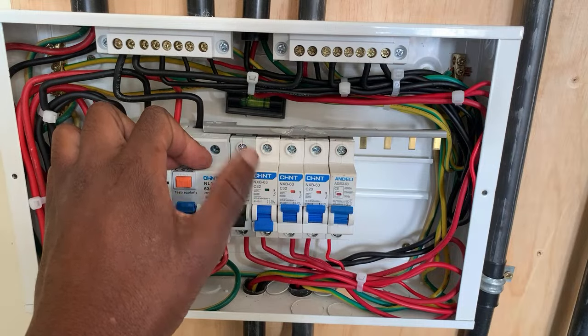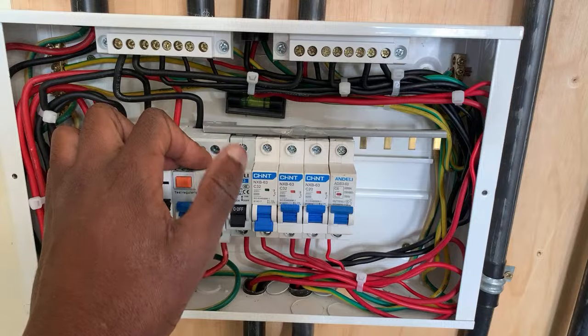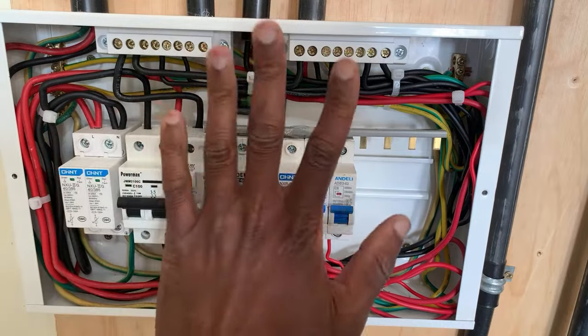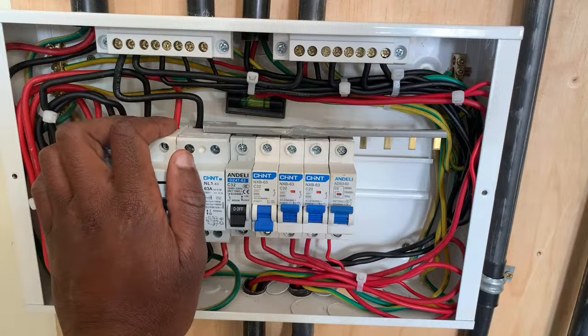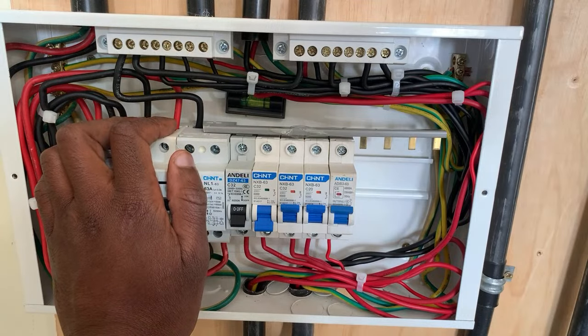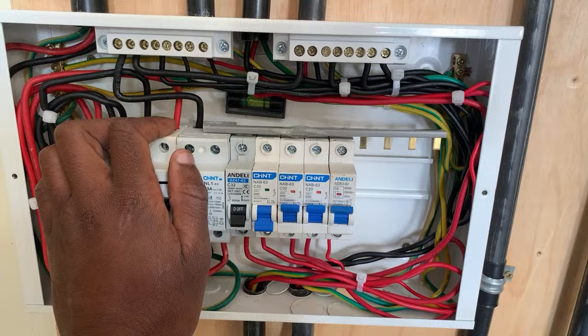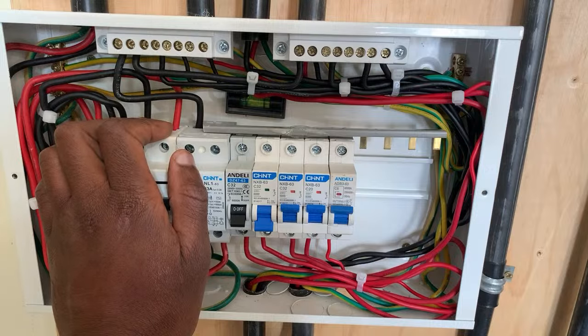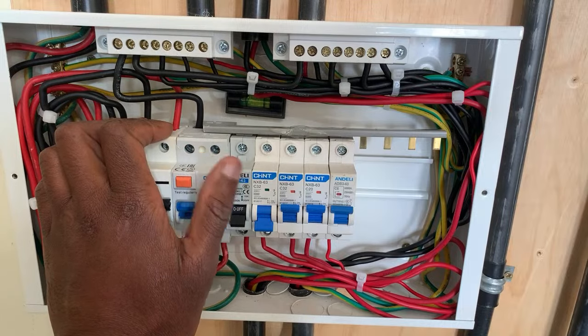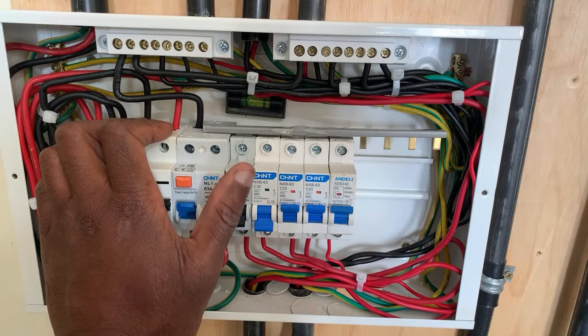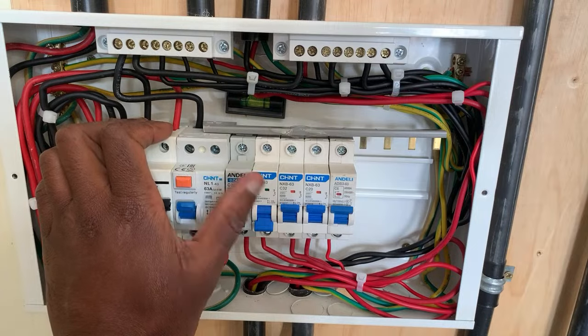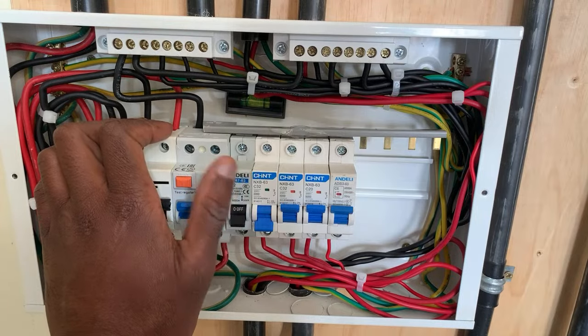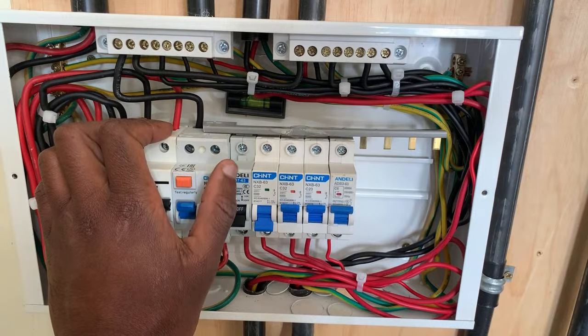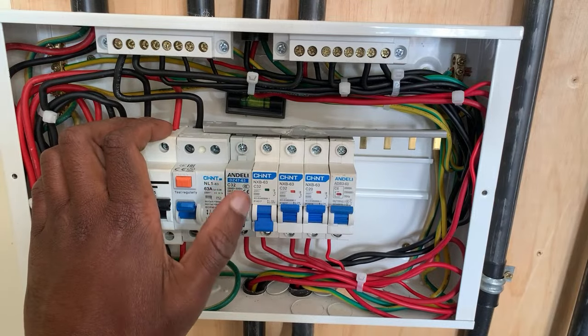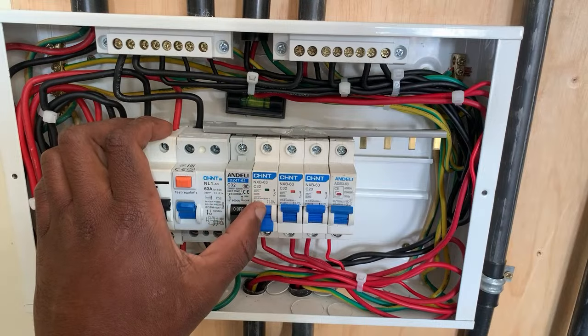So the main question should be, what specific circuit is not working? You don't start here, you start with the circuit that is not working. Is it the pump which is not pumping water? You ask those questions. At that particular time, you have already visited your customer. Is it the pump? Is it the electric cooker? You go and disconnect. Now, after you have disconnected, your job is not done. You should not lift this circuit breaker up.